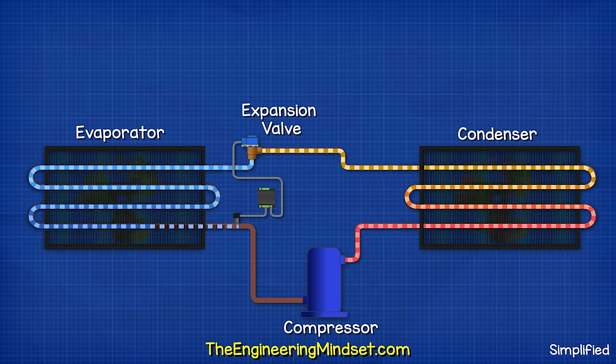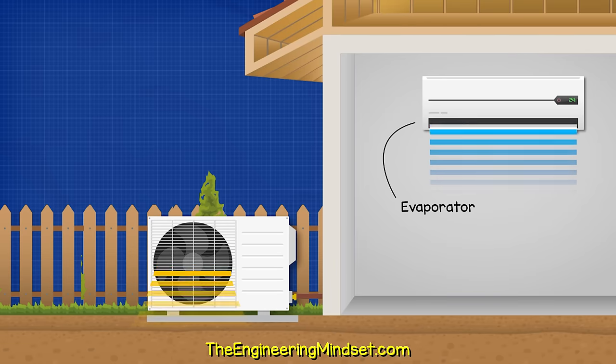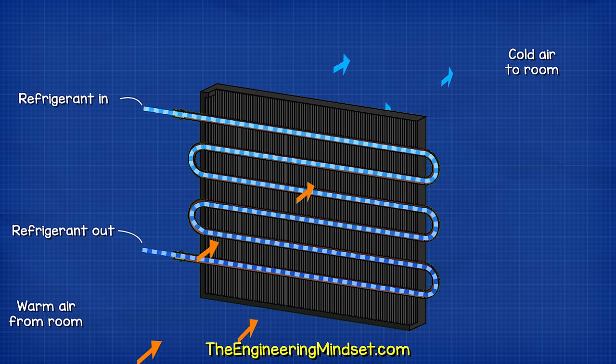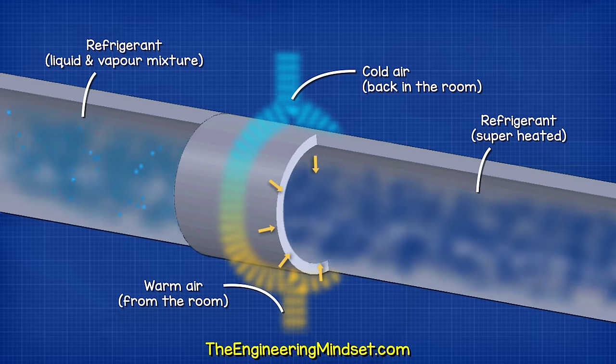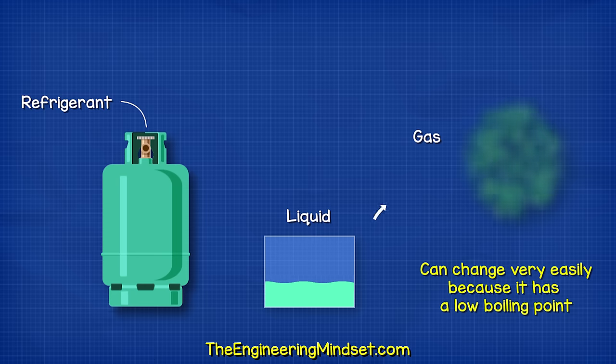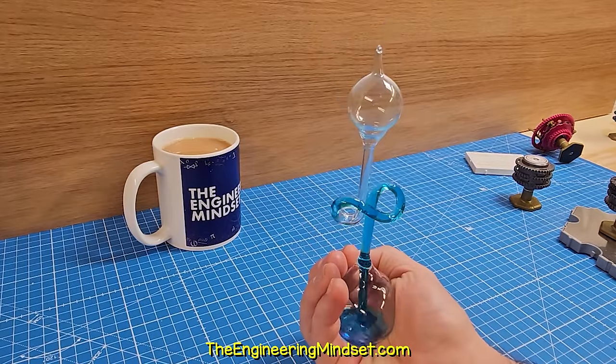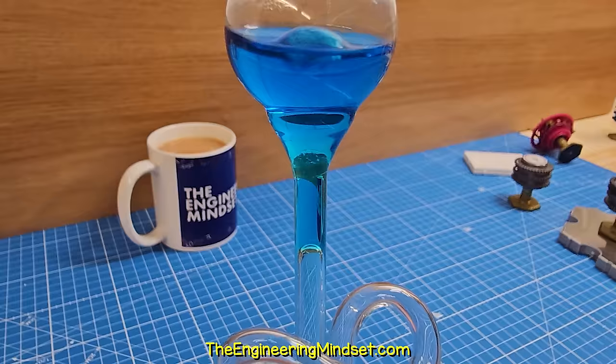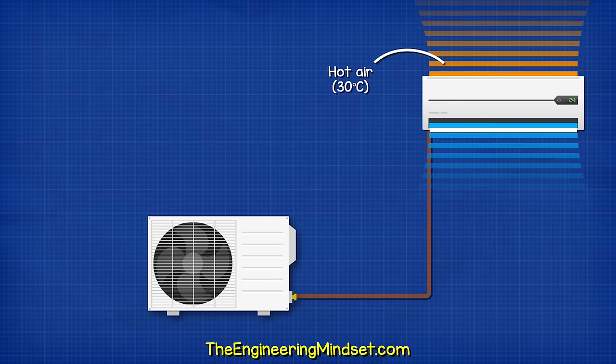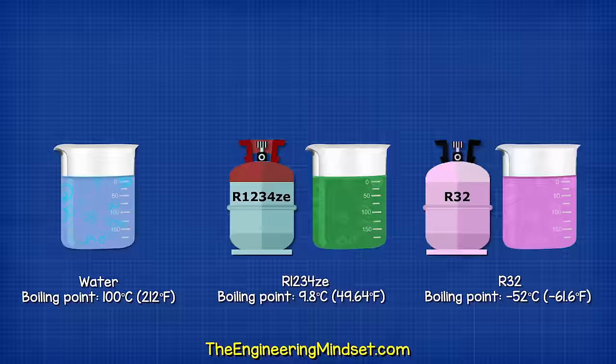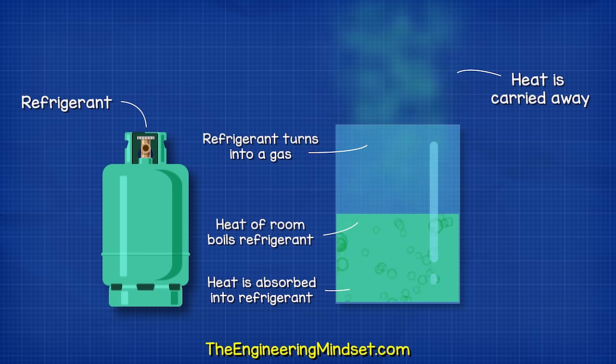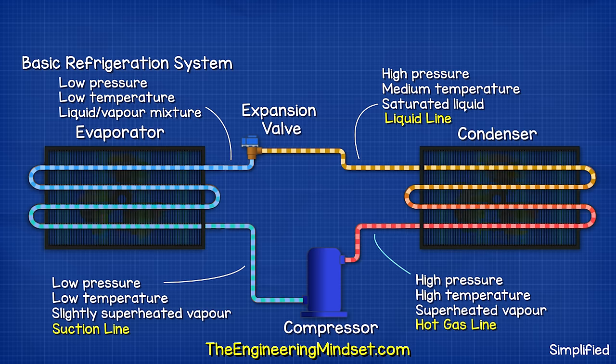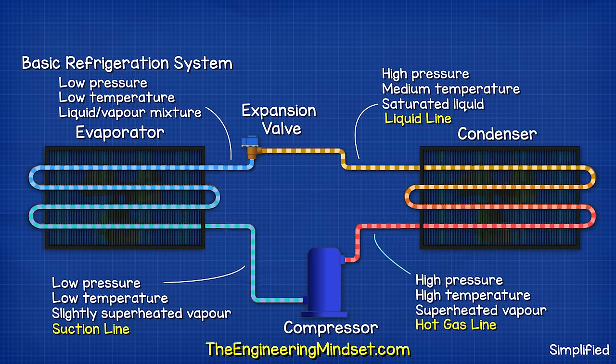This then flows into the evaporator, which is another heat exchanger inside the property. The refrigerant again flows through the tube, with the air of the room flowing over the tube. But this time, the thermal energy of the air is going to flow through the tube wall and into the low-pressure refrigerant. The low-pressure allows the refrigerant to boil very easily, just like this vessel filled with low-pressure refrigerant. My hand has enough thermal energy to cause it to boil. So, the heat of the room is enough to boil the refrigerant because it has a very low boiling point. The refrigerant turns into a gas and carries the unwanted heat of the room away. It exits as a low-pressure, low-temperature, slightly superheated vapor. The refrigerant is then sucked into the compressor to repeat this process.